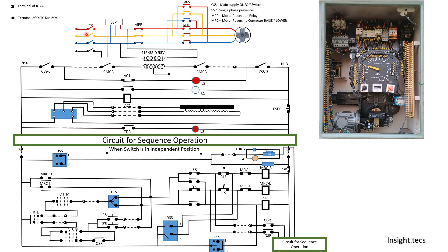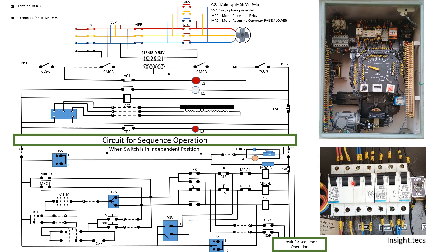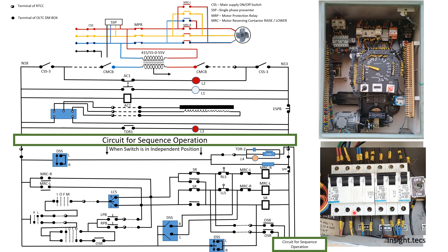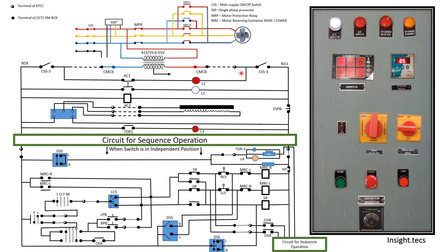We will start with the power supply from the CSS switch. Once you turn on this CSS switch, the power moves further and goes to the transformer, which is connected between the R and Y phase. Once it is energized, its LV side output goes to the circuit and reaches the CMCB switch. Once we turn on the CMCB switch, the power moves towards the RTCC panel.